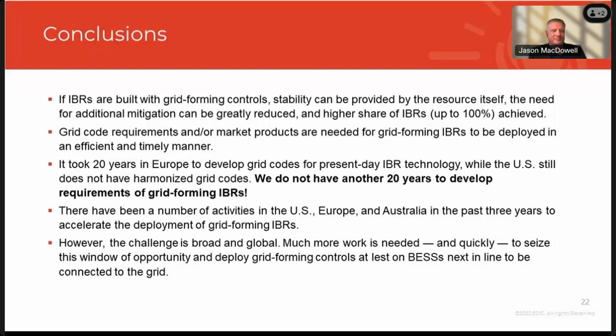I think from a control perspective, there is no difference. The control is on the inverter, right? So each one of these can be grid forming, but grid forming requires an energy buffer to provide this phase jump response, to provide what people call inertial response or rate-of-change-of-frequency limitation functionality. And for that there needs to be extra energy. This extra energy in a battery is already there. For solar, you need to back off solar production. You need to keep margin. So that means you're losing revenue as you keep margin on solar.